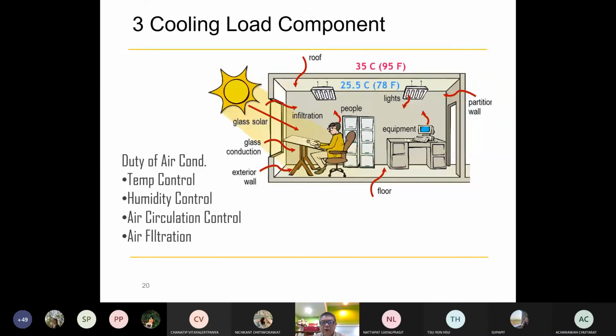Try not to use rule of thumb. Sometimes people simply say, oh, this room we can use 600 BTU per square meter, this room we use 1000 BTU per square meter. You can have that kind of rule of thumb if you don't have anything on hand, but you have to use it carefully and have some experience to use it effectively. But for a designer with no experience, I believe they should do a real calculation of the cooling load.